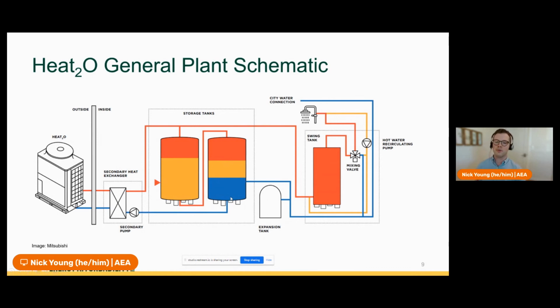At this point, I'm going to assume folks here are familiar with a single pass heat pump water heater and not explain in great detail what that means. It's connected to a swing tank into the mixing valve, just like is becoming standard practice for central heat pump water heating systems.